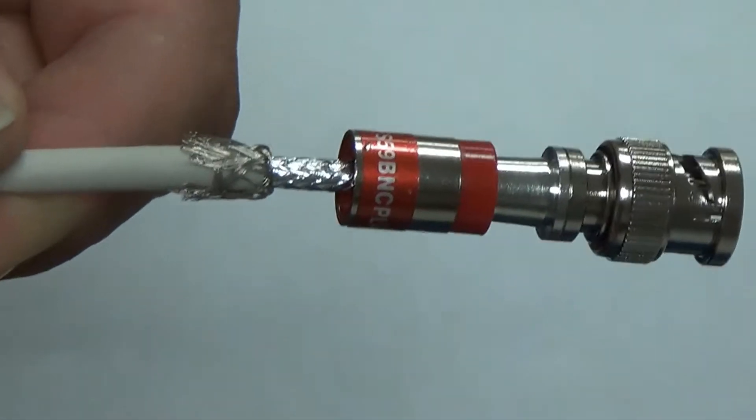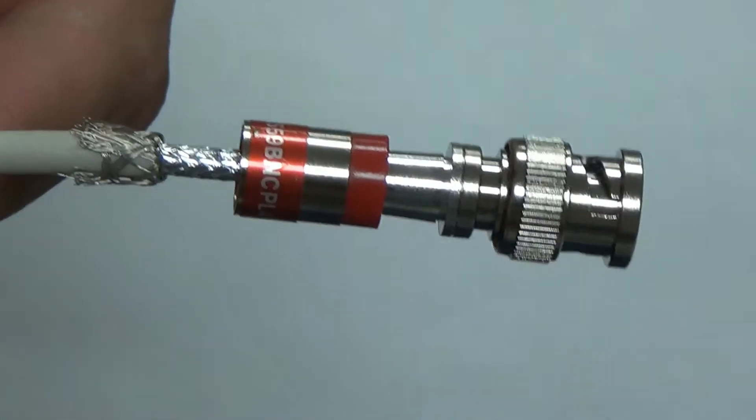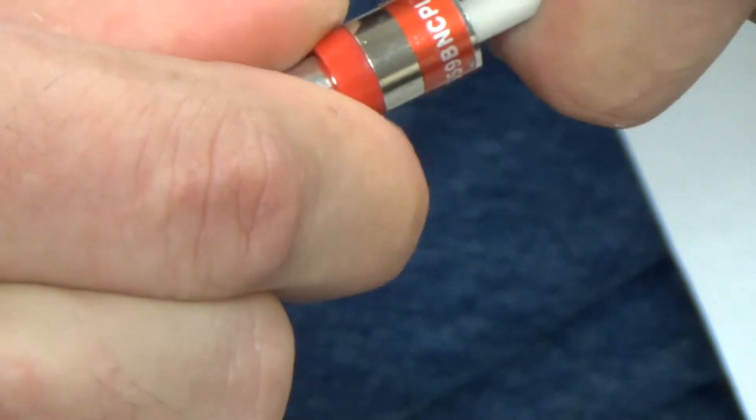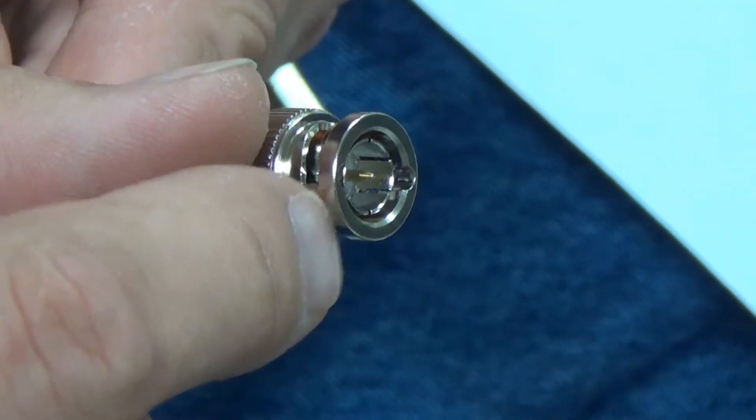That's going to come out the end when we push it in. Now this is the part that's a little tricky. When you push this thing in, it's a little hard, so you got to kind of work it down in there. We always say, just in technical terms, you got to use your big boy muscles to get it in. Once you push the connector down in, you can see the jacket goes right up inside there just like that. And you can see the center pin's starting to come through right now, but we need that center pin to get all the way up here to the top. So basically you push and twist, just keep pushing and twisting, push and twist, push and twist. And there it is. If you rub your finger across the top, you should just be able to feel that center pin just right there, just barely protruding past the top of the connection. I mean barely.